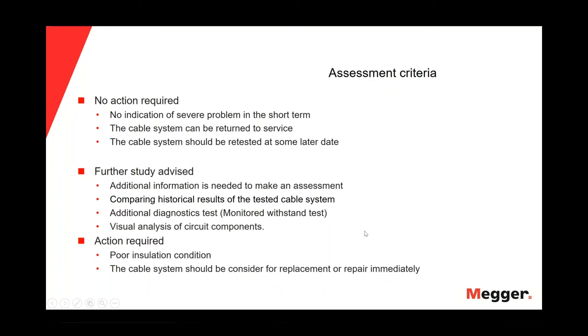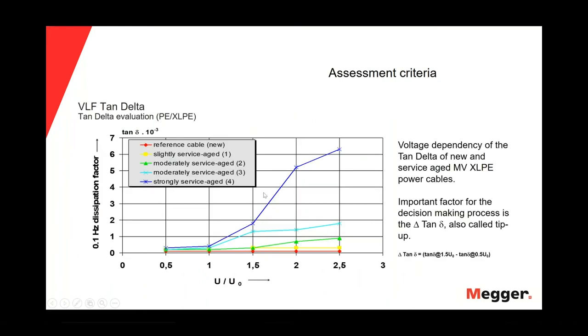So, continuing with the assessment criteria, we can see that for XLPE insulation there is a voltage dependency. For instance, in this graphic, we can see that for a new cable or a reference cable, that is the red graphic that we have here, we have almost a flat line, okay? But if we see the blue one, that is the graphic for a strongly service-aged cable, we will see an increase of the values of the tan delta as we increase the voltage. So that means that we have a voltage dependency of the tan delta of new and service-aged medium voltage XLPE cables.